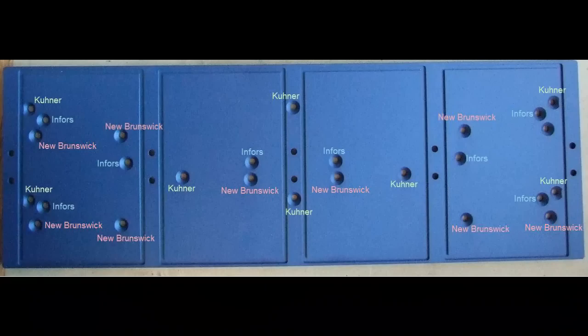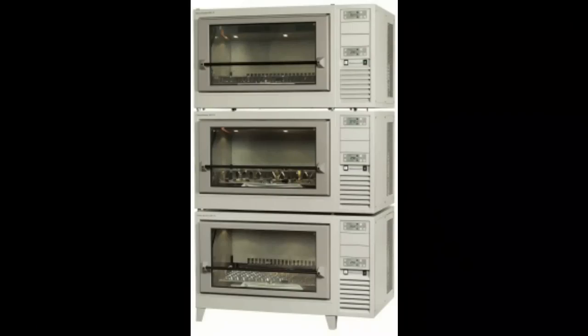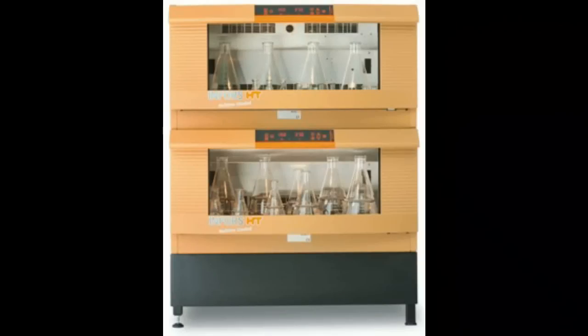The ground plates of the clamps have different hole patterns for different shaker types. The hole patterns are compatible with shakers from Kühner, Infors, and New Brunswick.